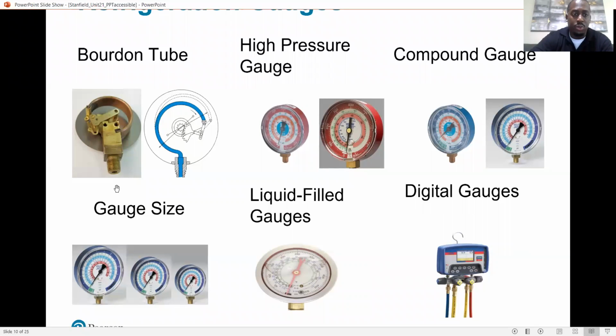It has this Bourdon tube on the inside. And so when the refrigerant pressure goes into the orifice and fills the Bourdon tube, it's going to expand. It's going to open up. And when it does that, it's going to turn these gears, and on the other side of that is a needle, which you can see in this illustration. And so as this opens up, it's going to turn that gear, and that needle is going to start to move. And then when the pressure is reduced, like when you take your gauge off, or if the system changes, like if the system turns off and the compressor is off and the pressure starts to balance out, this Bourdon tube will start to contract, and then it's going to move the needle back in the opposite direction, going back towards zero.